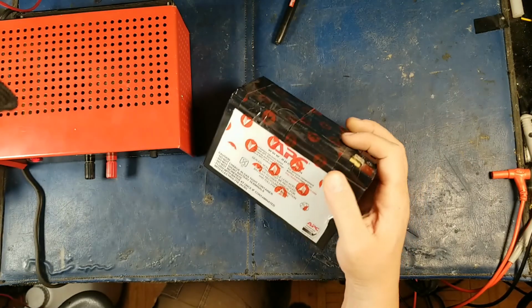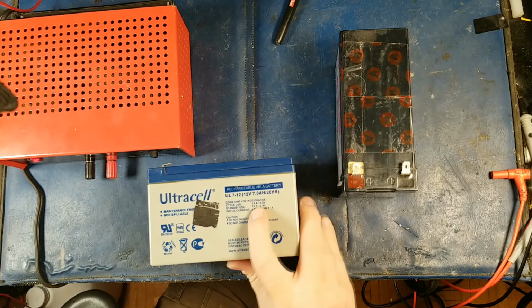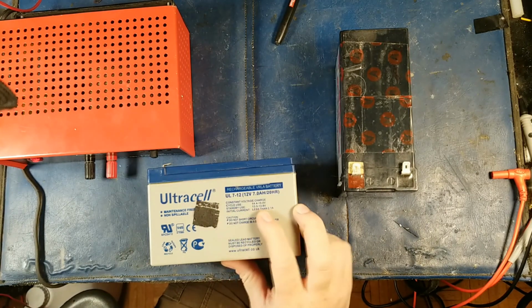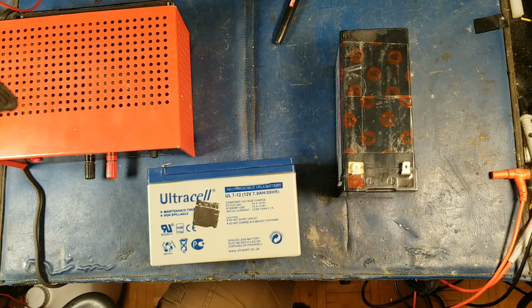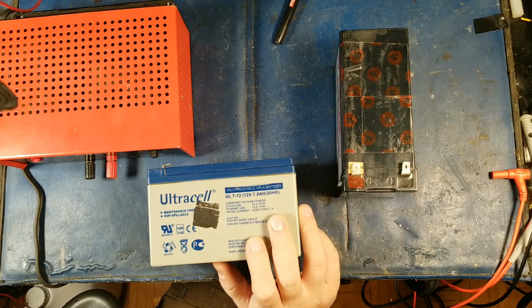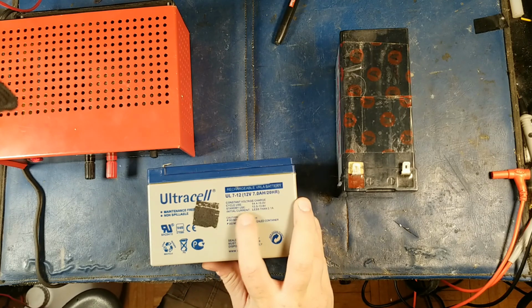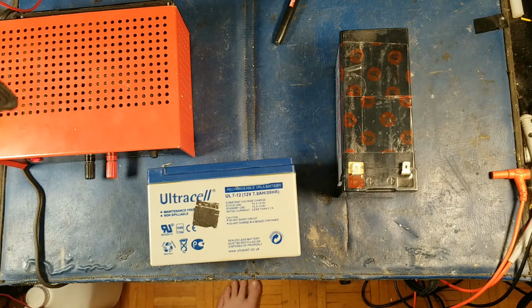If you look on these batteries, they tell you what they need. Here we can see the cycle use is 14.4 to 15 volts — that means if you stick it in a system, it can operate at those charges. That's overflow. Now if this is standby use, you want to keep it at a float charge so it doesn't overcharge, ruin the plates, and create hydrogen sulfide gas. If it gasses, you lose your moisture, and if you lose your moisture, your battery dries out and it's toast.